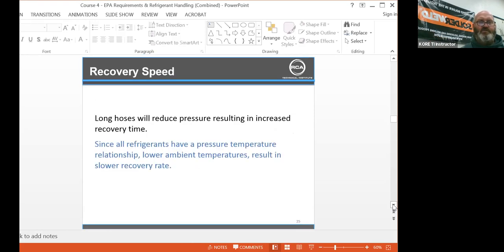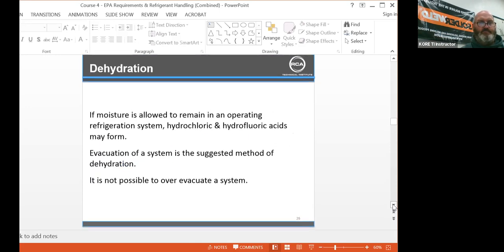Long hoses will reduce pressure, resulting in increased recovery time. Since all refrigerants have a pressure-temperature relationship, lower ambient temperatures result in a slower recovery rate. Obviously, you guys know that already, especially you guys living in the northern states, you know about it.